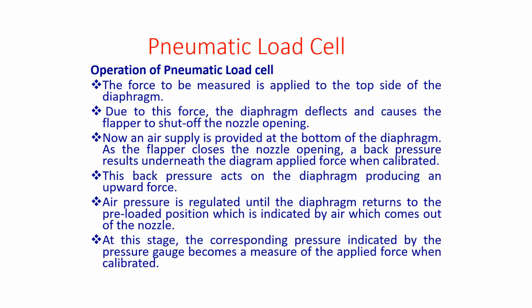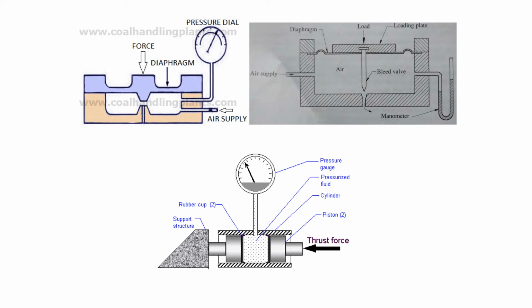This back pressure acts on the diaphragm, producing the upward force. So the diaphragm comes back to its original position. At this stage, the corresponding pressure indicated in the pressure gauge becomes a measure of the applied force when calibrated. If you look at the diagram, you can easily understand that when the force is applied on the diaphragm, it gets deflected, and the same is shown in the pressure gauge. And again, air will be supplied from the bottom, and the diaphragm will come to its original position.